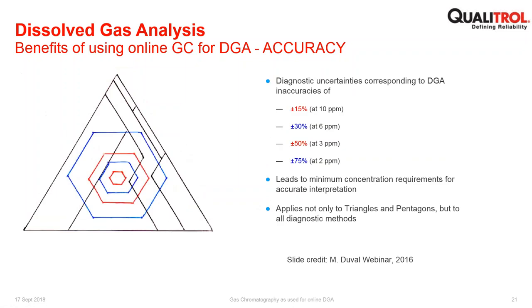If accuracy really is of poor quality, or you're down at very, very low concentrations, then the areas can get very, very large, to the point where, if accuracy at a level of 2 ppm is plus or minus 75%, you cannot necessarily rely on any diagnosis. And that's why Duval triangles and pentagons should be used only when concentrations start to get appreciable, so in the tens or hundreds of ppm. Because at very low concentrations, where you're driven by lower detection limits, inaccuracies can lead to inaccurate diagnosis.